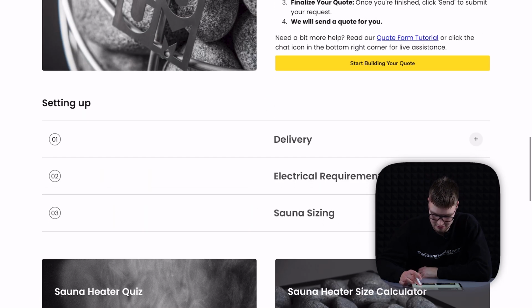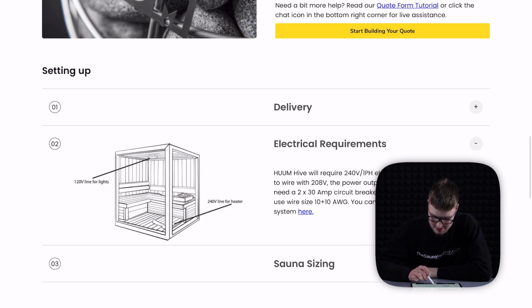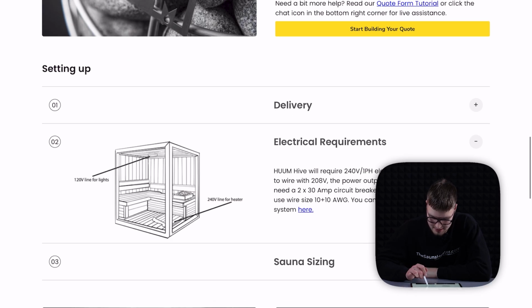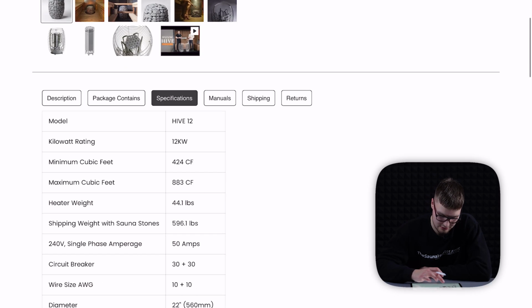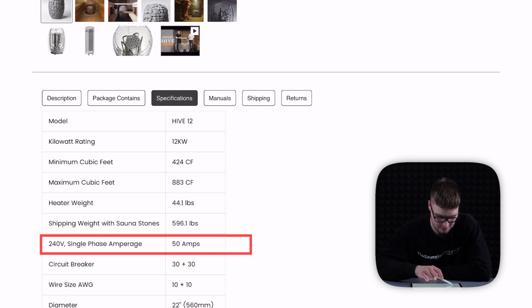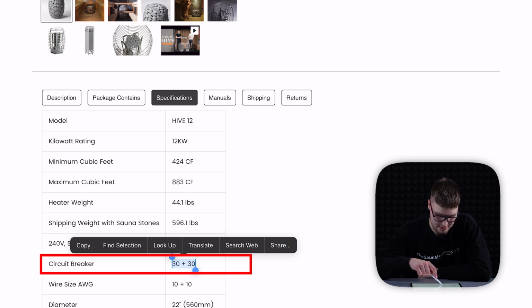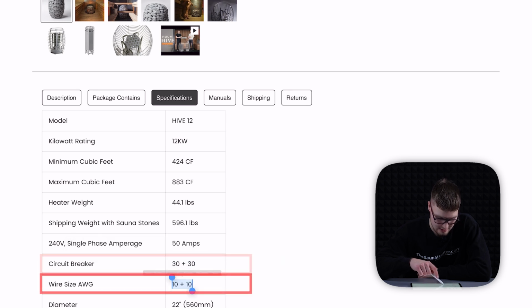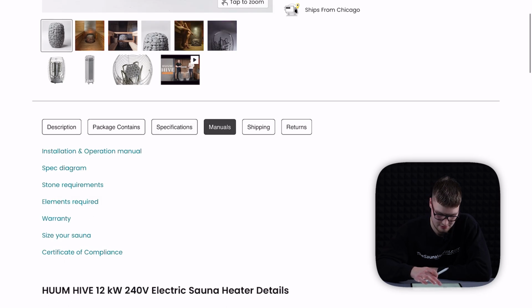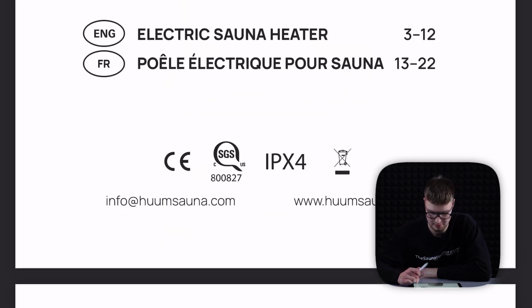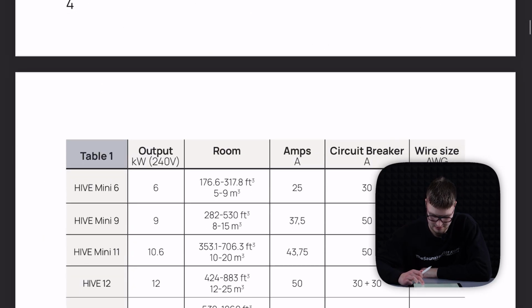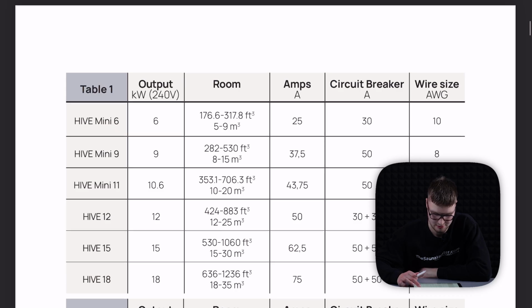When you scroll down, you see electrical requirements listed right there. Or you can check specifications: 240 volt single phase, 50 amps amperage. For circuit breakers you need 30 plus 30, so two 30 amp circuit breakers, with wire sizes of 10 AWG for both. You can also go to manuals, installation and operations manual, and scroll down to see all the electrical information in a table.